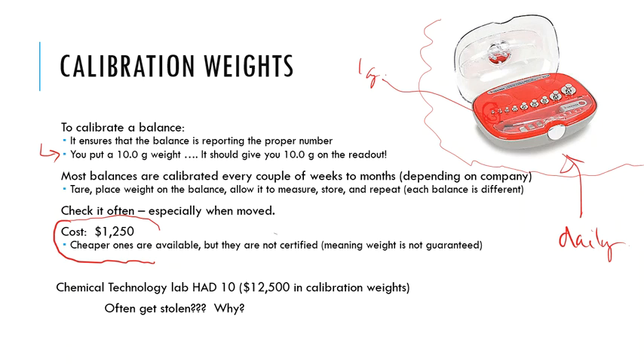But the problem is that they are not certified. So what this means is that a proper certified calibration set would be, okay, this is 50 grams, and this has had extremely intensive tests by third-party organizations that is 50 grams, just the way it's stated on the calibration weight. That is what a certification means.